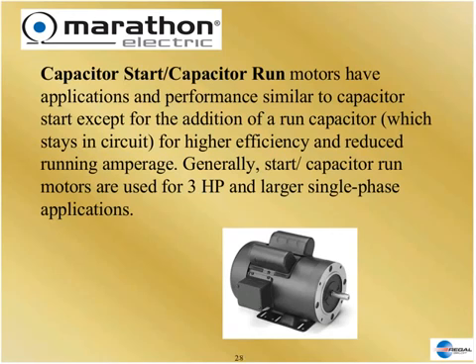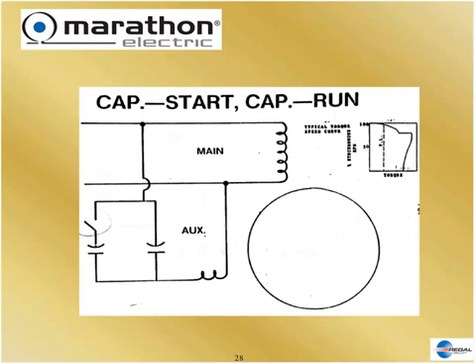There's another single-phase concept where we put a second capacitor in — called the two-value motor. This motor is specially designed to get more performance out of the running end. The speed-torque curve looks similar, but the switch only removes one of the capacitors; the other stays in the circuit all the time. Now our auxiliary winding helps in the run condition to produce better efficiency, lower amps, and more horsepower. That's why pump people really enjoy this motor — they get more horsepower from the same size motor.